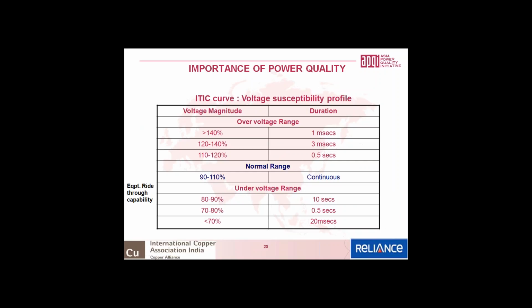Now, I'm showing some curves, but these are not specifically about harmonics. All electronic equipment is designed to withstand supply variations. The normal range is around 90 to 110 percent. But the tolerance to the over voltage range is extremely limited. Utility faults can occur anytime, and there will be a voltage dip during the fault in which the voltage will go below 70%, and the fault has to be cleared by a breaker whose operating time cannot be less than 20 milliseconds. It will be more than 20 milliseconds.